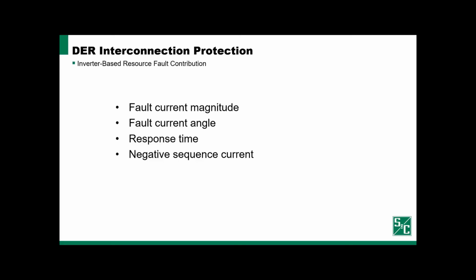Another significant factor is fault current angle. With conventional sources, we could assess the magnitude and angle of the fault current by considering a Thevenin equivalent source, where we have a voltage source behind an impedance, and the impedance of our rotating machine plus the impedance of the system between the machine and the fault would drive both the magnitude and angle of the fault current contributed. With inverter-based resources, this can be different. The angle of the fault current can often be driven by the control mechanisms and algorithms in the inverter, which can drive significantly different angular and magnitude responses to faults depending on the settings configuration of an individual inverter, as well as the controls programmed into it by its manufacturer.